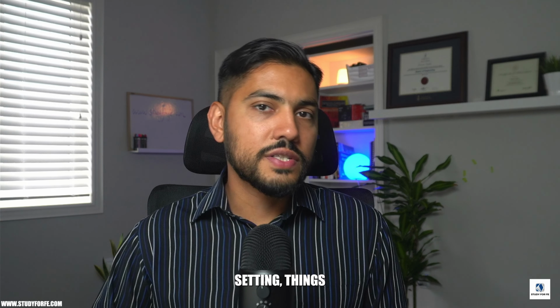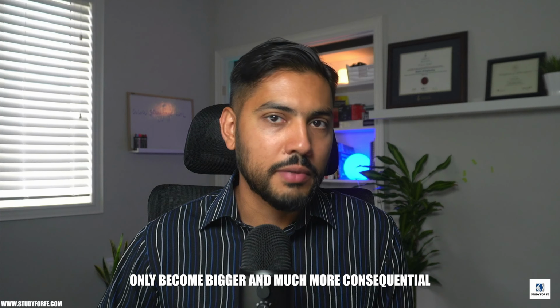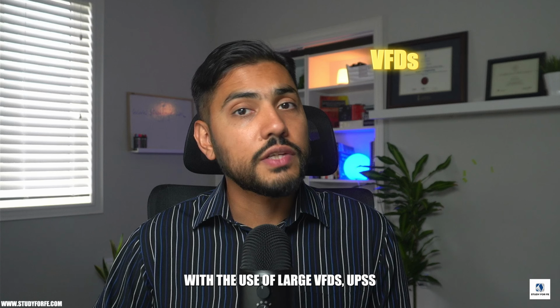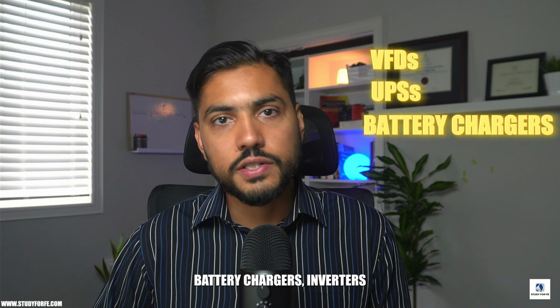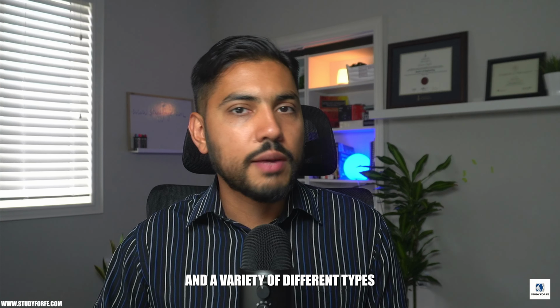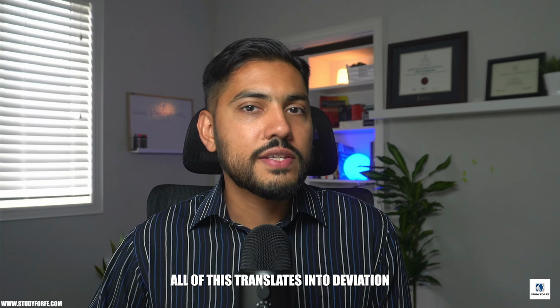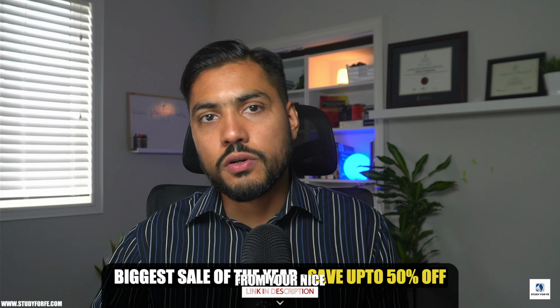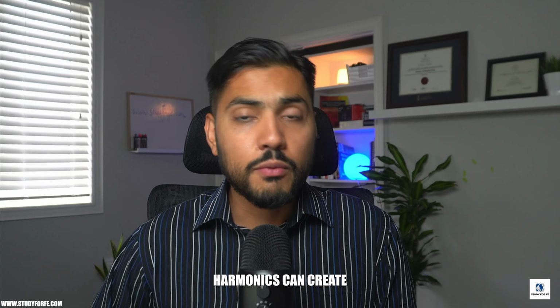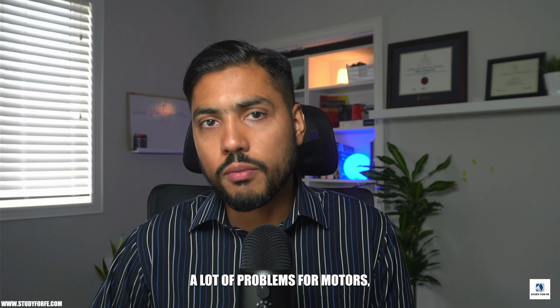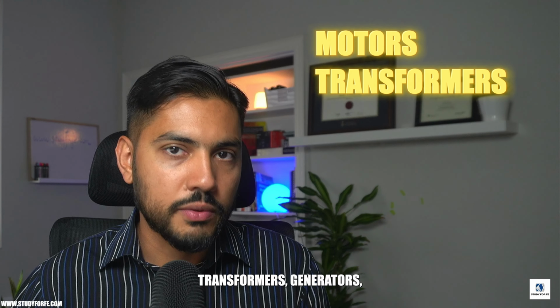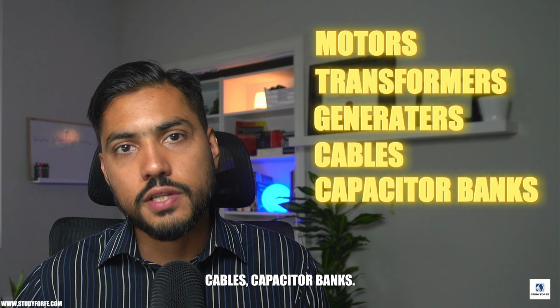All of these loads have non-linear components in them which produce harmonics. And obviously in the industrial setting, things only become bigger and much more consequential with the use of large VFDs, UPSs, battery chargers, inverters, and a variety of different types of power electronic equipment. All of this translates into deviation from your nice looking sinusoidal waveform for voltage and current. Harmonics can create a lot of problems for motors, transformers, generators, cables, capacitor banks.